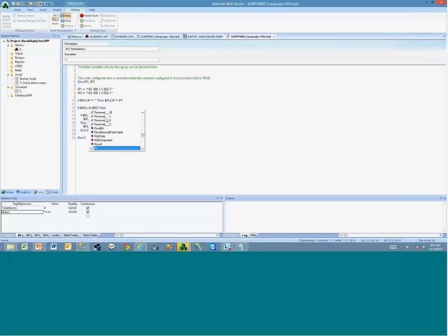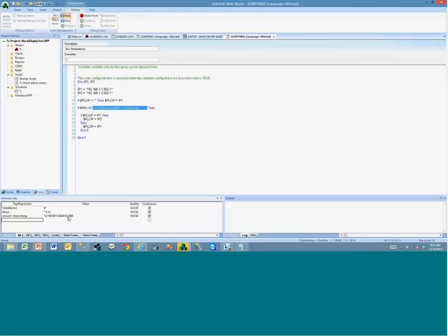So you can use here the read status timestamp, which is the last time that this tag changed value. If you use this function strGetElement with .1, you retrieve the timestamp. You remove the milliseconds from the timestamp, because if you see here the timestamp format, it has the date and time, but in the time there is a dot before the milliseconds. And this function strGetElement, using dot as the delimiter and returning the first element, returns the timestamp without the milliseconds, which is the format supported by the VBScript datetime functions.